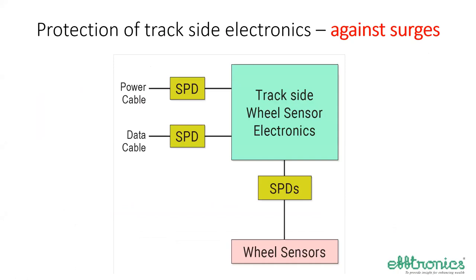So for the trackside electronics of the wheel sensor, that is the axle counter, the manufacturer suggests that if you want to protect it, then SPDs are to be provided. Surge protection devices. They are connected towards the wheel sensor cable, towards the data cable, which is going to the next wheel sensor, and then to the power cable. All three are to be protected.